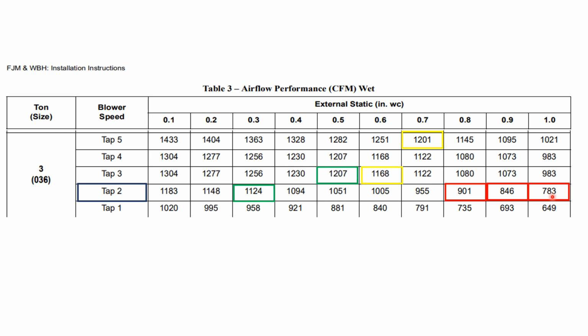Some compressors actually put out, say they're 32s or 31s, but with the coil size that they have, it will produce 36,000 BTUs. Now, what I have to do is also understand that in that air handler, that coil, the indoor evaporator coil, is a certain size tall, a certain size wide, and it's made with a certain amount of fins across it to allow, if I have 1,200 CFMs blowing across that size coil, it will produce 36,000 BTUs.